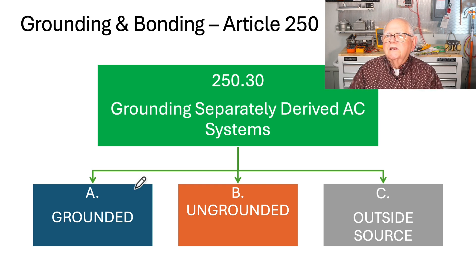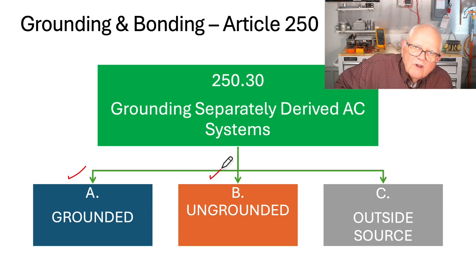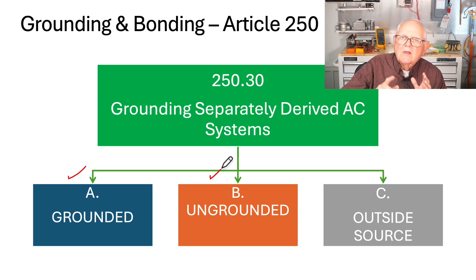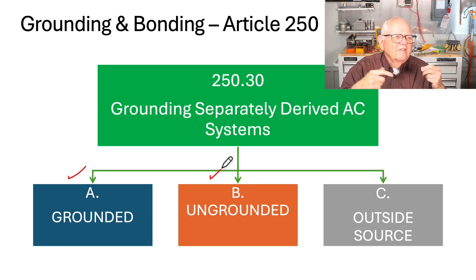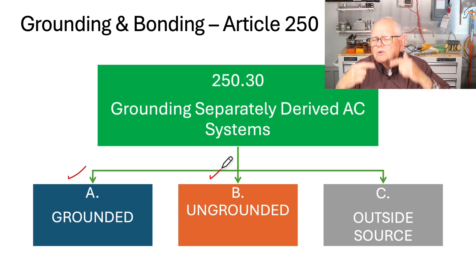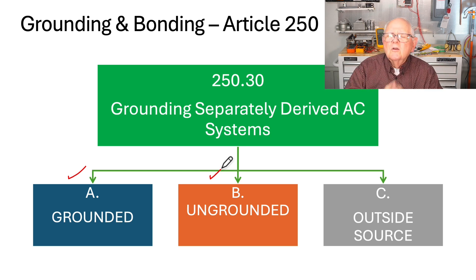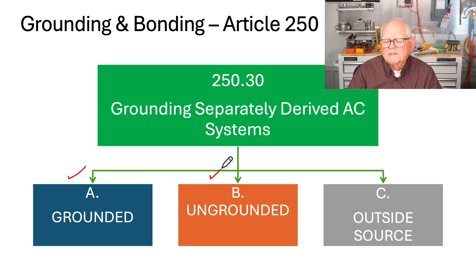Section 250.30 is divided into three separate sections. Section A is for grounded systems and Section B is for ungrounded systems. At the very beginning of 250.30, it tells you to be sure and apply 250.20 and 250.21 — which cover systems required to be grounded, systems permitted to be grounded, and systems not allowed to be grounded. Most typically we're dealing with grounded systems and are in subsection A, but B addresses ungrounded systems.